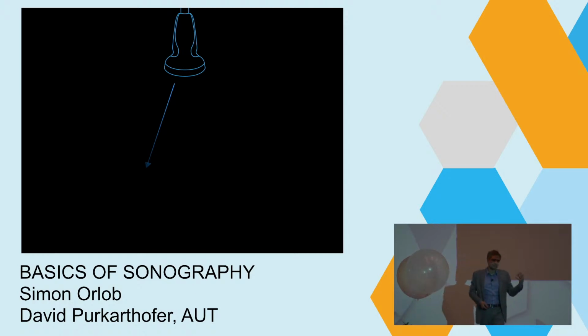Now think of an ultrasound beam. It's traveling through the tissue, and all the time some echo is coming back. So it's losing energy in depth. At first, very much energy, and later it's less. And the ultrasound machine compensates for it. It knows if I'm at a depth of 10 centimeters, I have to enhance the echo a little bit. So the liver looks the same at 10 centimeters depth as at 1 centimeter depth. And so also the echoes are less, obviously.